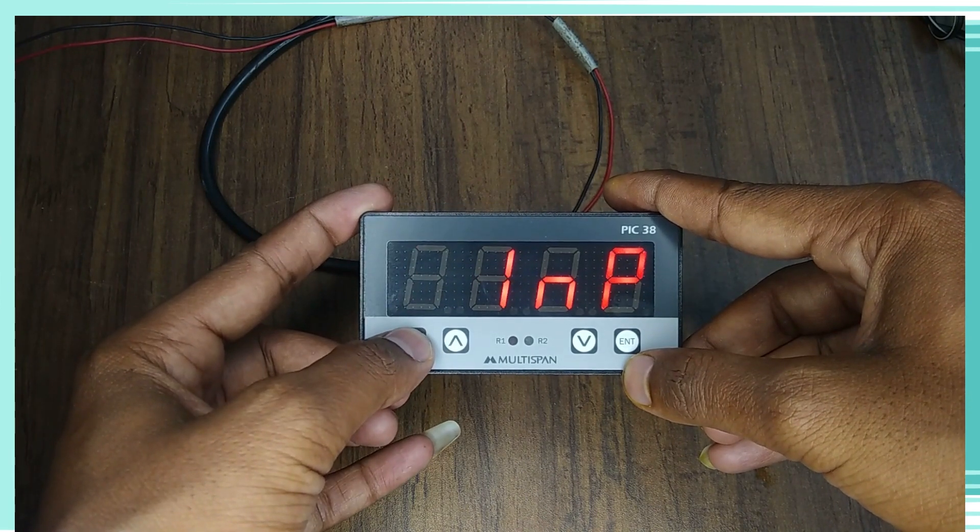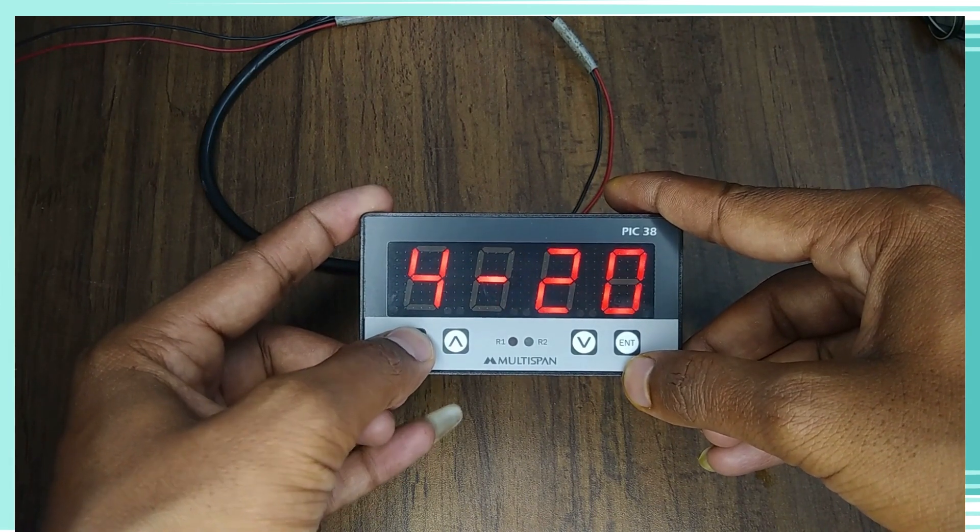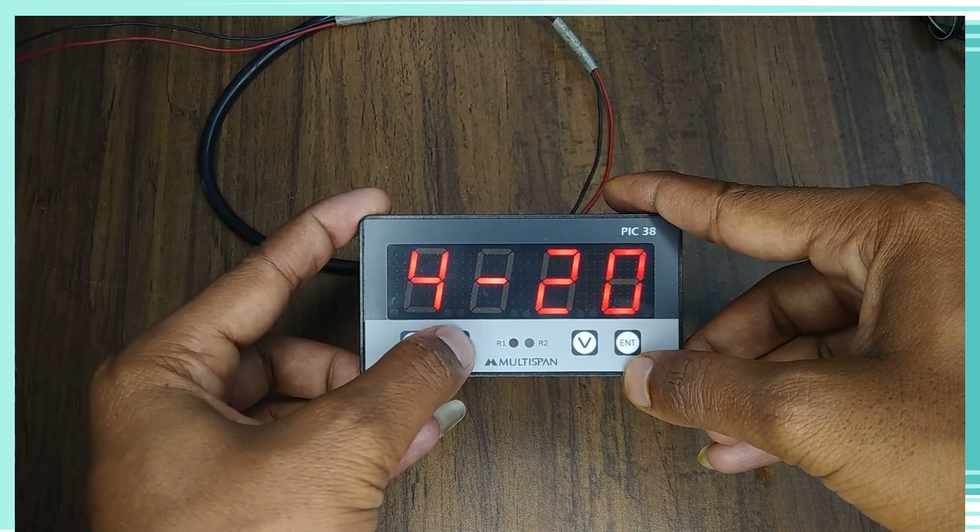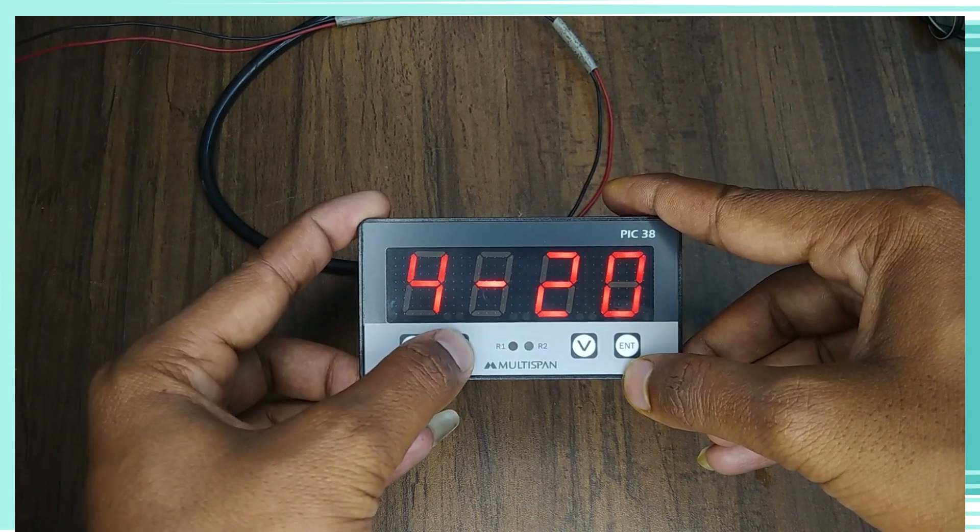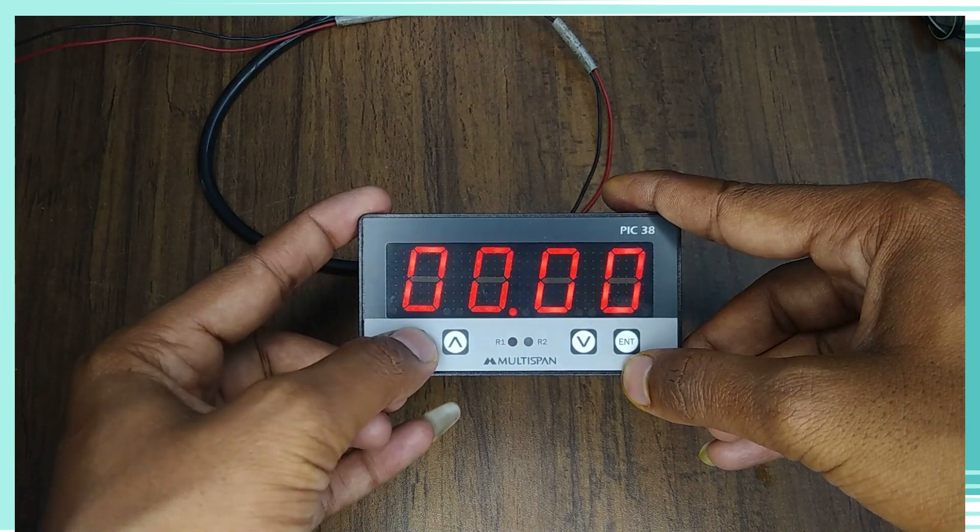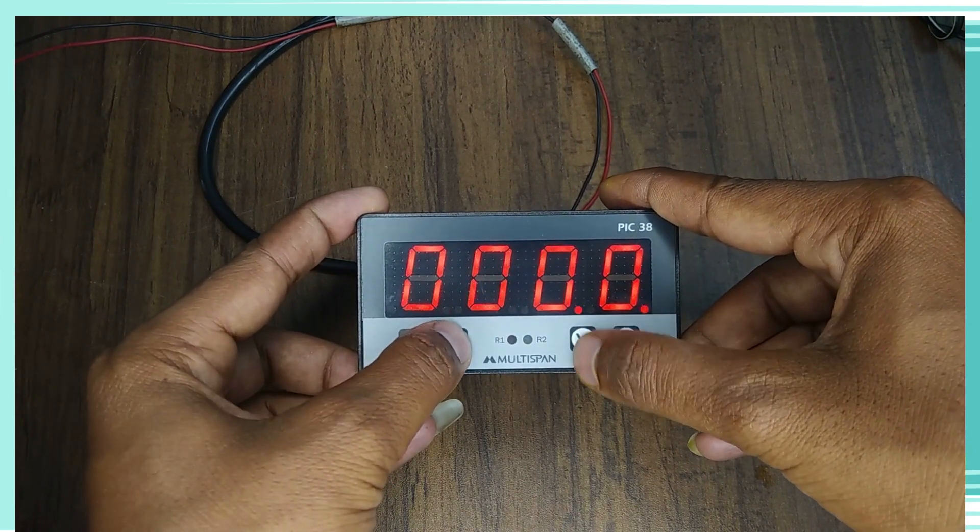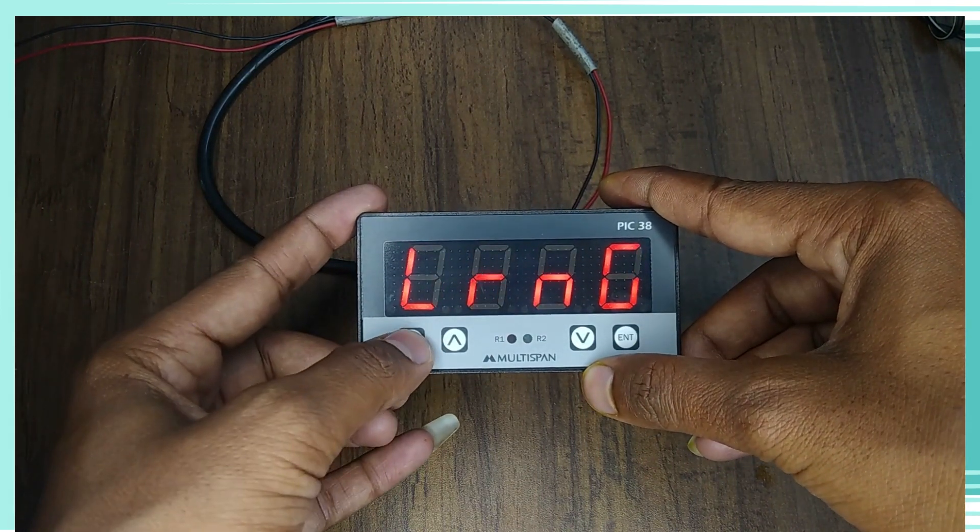After that in the input, we can set up to 0 to 20, 4 to 20 milliampere DC and 0 to 10 volt DC. Next set press key is decimal point. In that, you can change the decimal point.